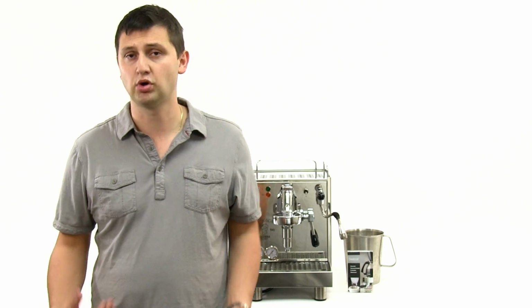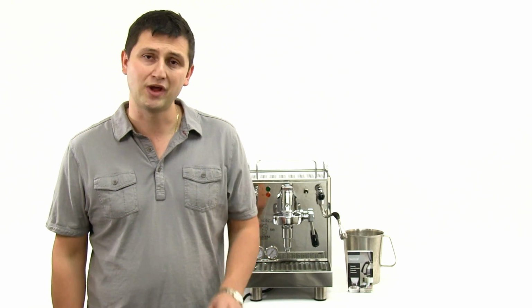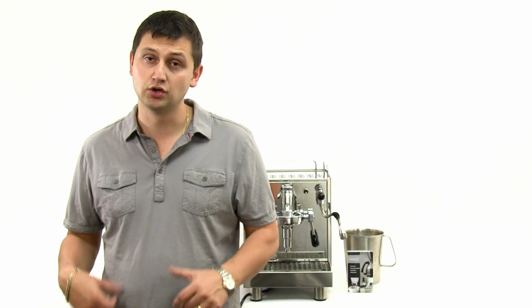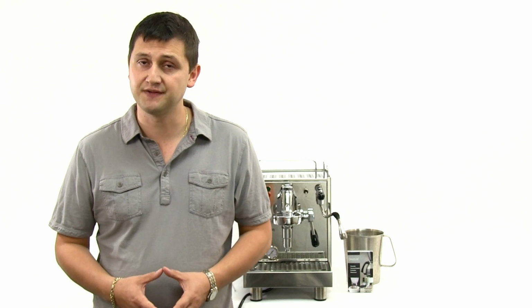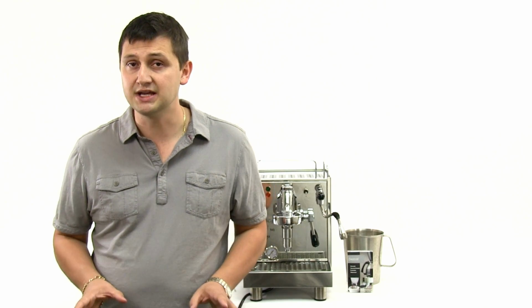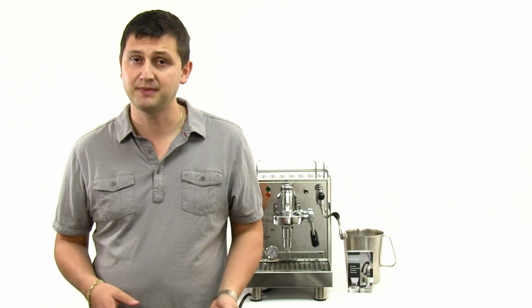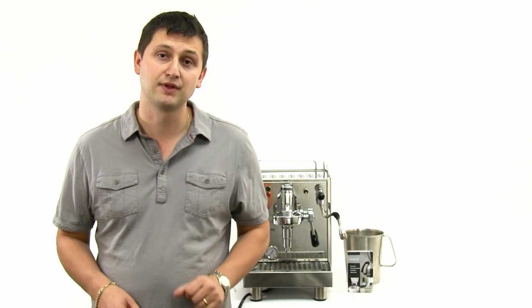To do a full and proper descale of a heat exchanger, we have to overfill the boiler. And in order to do that, we have to disable the level probe. Now all this can sound difficult and intimidating, but it really isn't. Just follow the steps in the video, do this every 90 days, and your machine will run for a long time to come. So the first step that we need to do is disable the level probe.